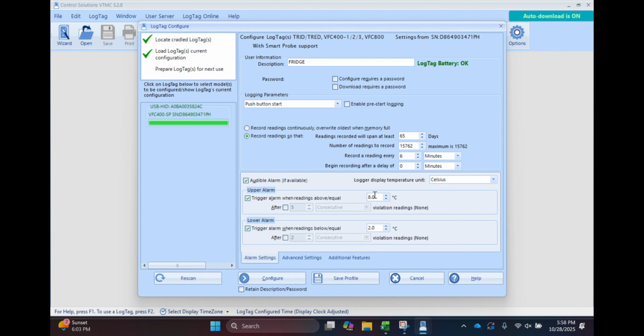If you wanted to do a freezer, you could replace the alarms with -15 for the upper and then -40 for the lower, and in that case you would simply need to rename the fridge to freezer. The only thing that separates a fridge logger from a freezer logger is the name and then the alarm values you program into it. So these would be the freezer settings at the CDC values that would be ideal. You may pause the video on either screen if you need to retain the settings for longer.